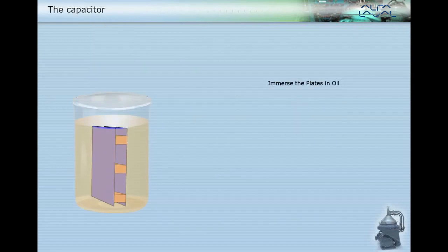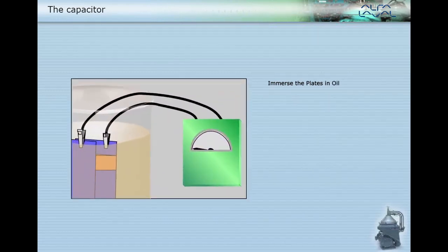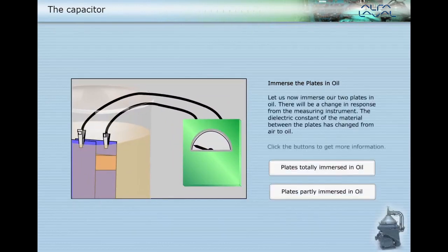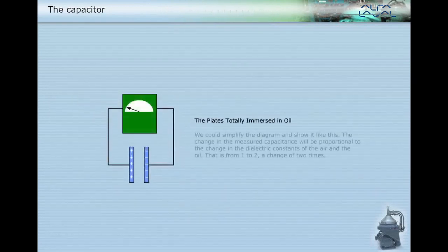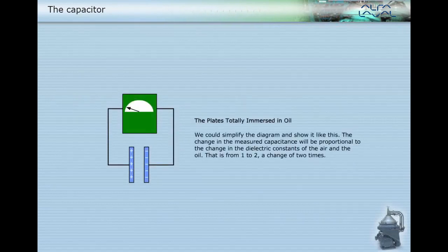Let us now immerse our two plates in oil. There will be a change in response from the measuring instrument. The dielectric constant of the material between the plates has changed from air to oil. Click the buttons to get more information. We could simplify the diagram and show it like this. The change in the measured capacitance will be proportional to the change in the dielectric constants of the air and the oil, that is, from 1 to 2, a change of 2 times.